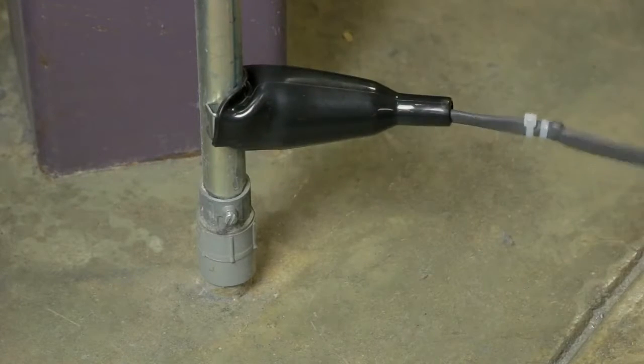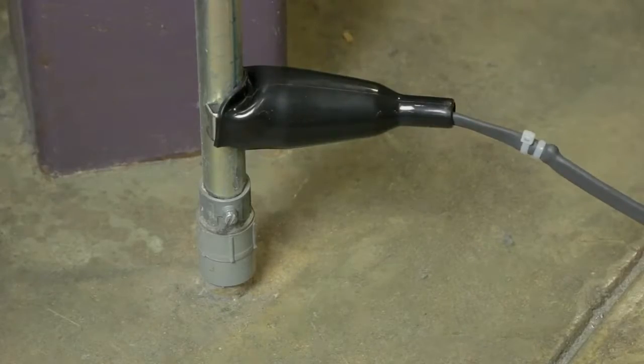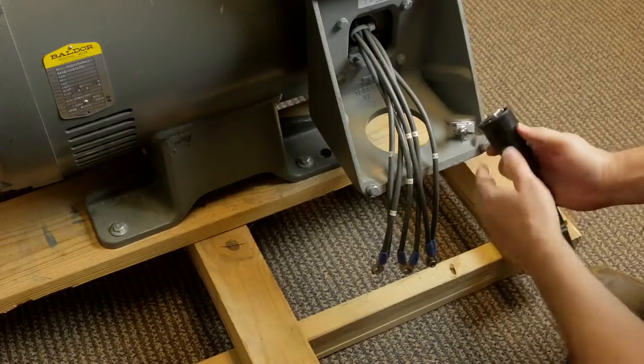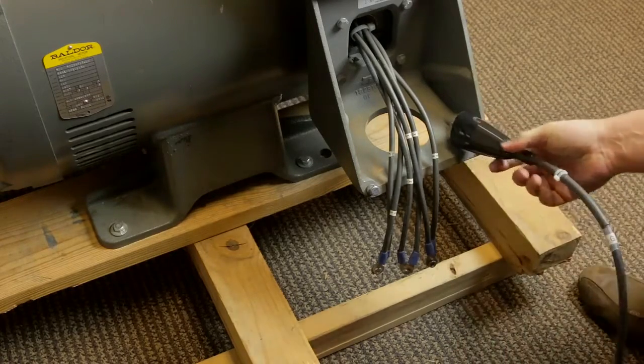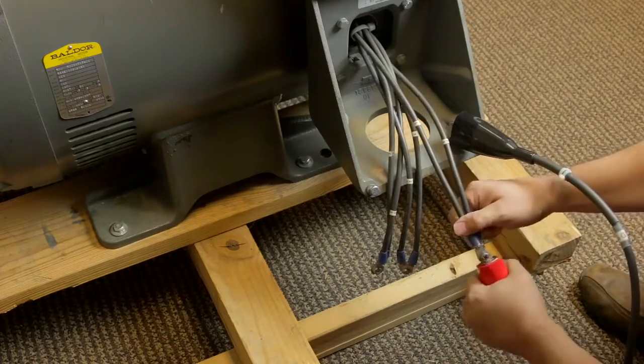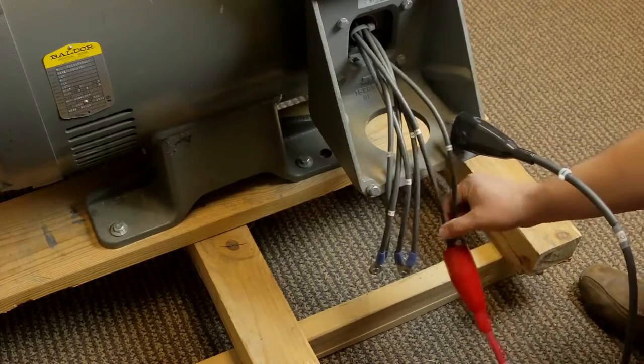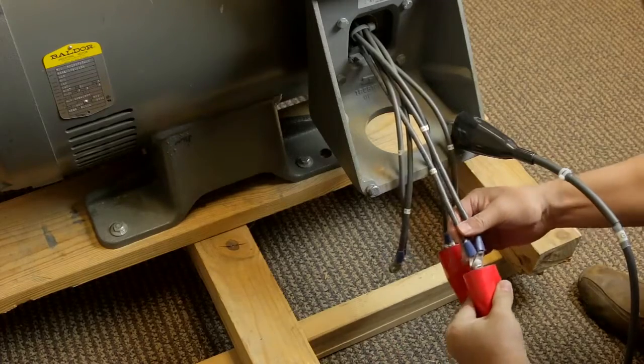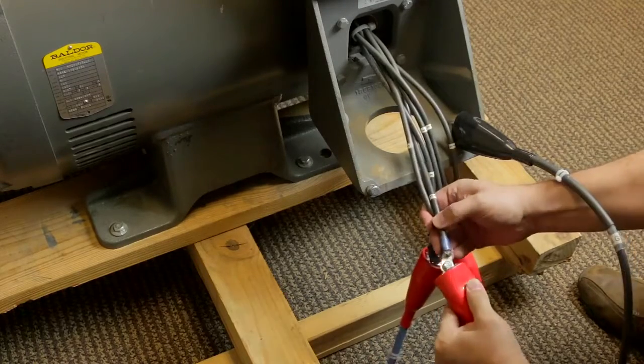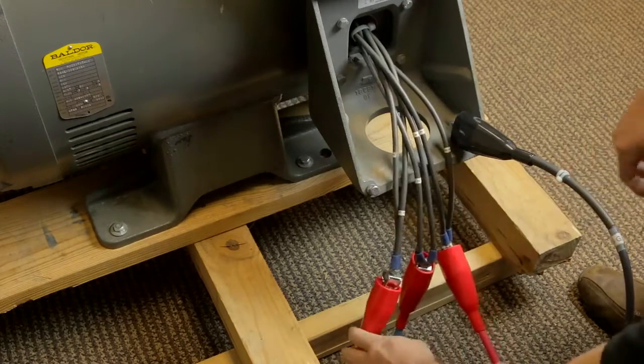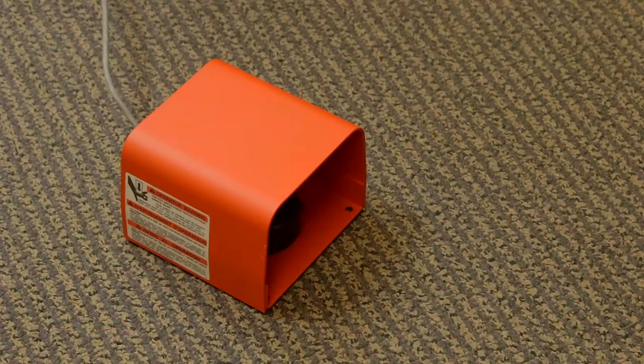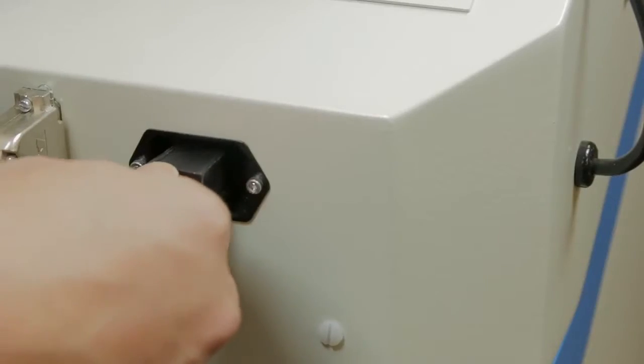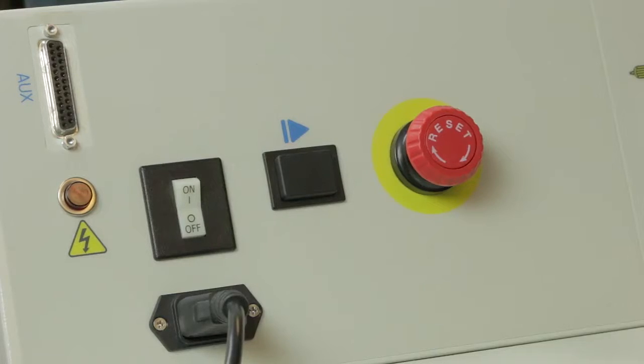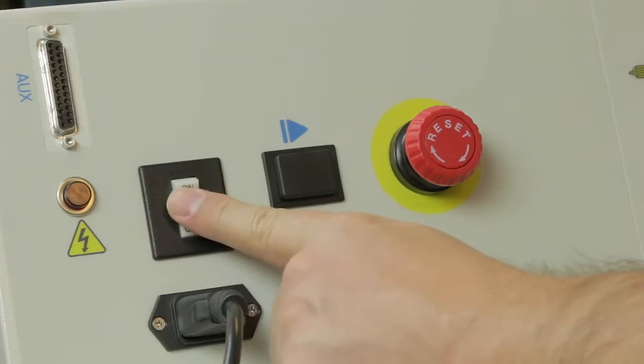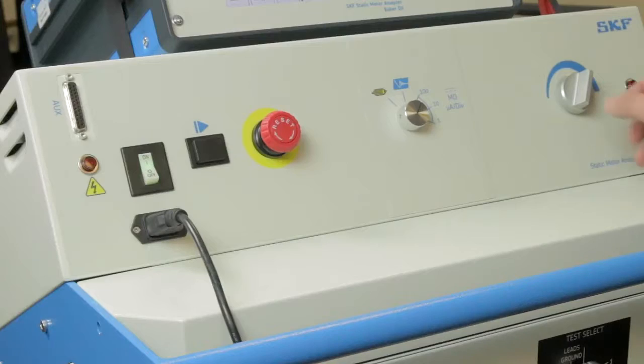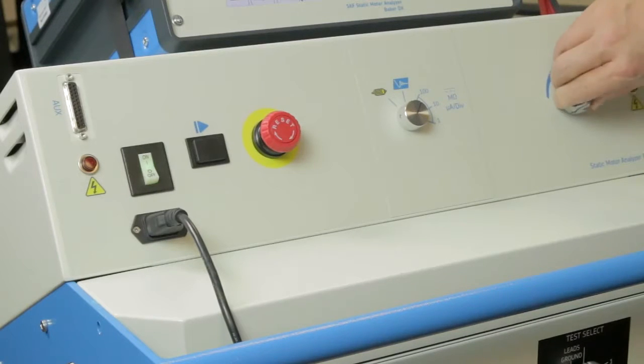Connect the braided ground cable to a known earth ground point. Connect the test leads to the motor's stator terminals and the ground lead to a paint-free point on the motor's frame. If you have the optional foot switch accessory, connect it now. Power on the power pack and the DX. Verify that the voltage control knob is set to 0.